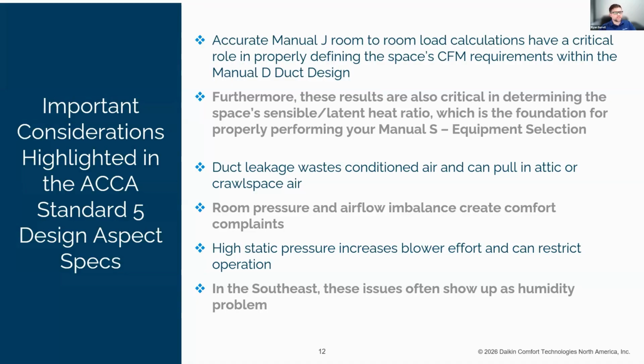Manual J room-to-room load calculations have a critical role in properly defining the space's CFM requirements within your Manual D duct design. So if you get that wrong, everything's going to end up being wrong, because those results are also a critical piece in determining your sensible-latent heat split ratio. And that's the foundation for forming your Manual S and selecting the appropriate equipment. We talked a little bit about room pressure and airflow imbalances, and how those create real customer complaints.